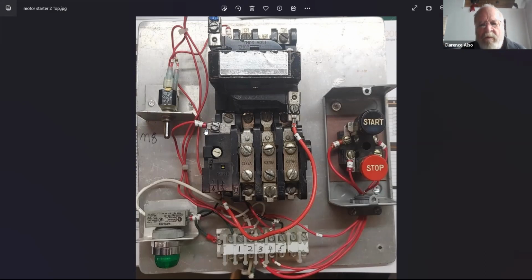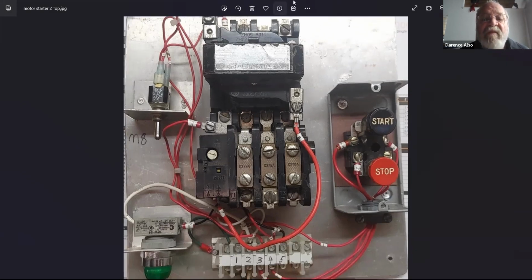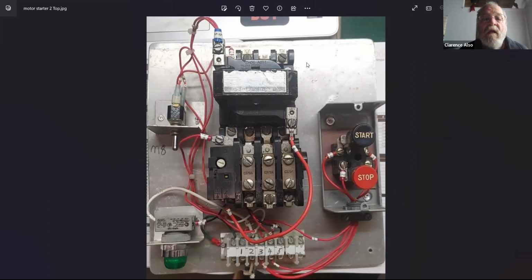On the circuit we're doing, I think we're calling this M9. So anyhow, you had M9 auxiliary contacts, M9 the coil. This is the coil there. You can see a number 6 going to the right side of the coil, and if we went up a bit more, you'd probably see 5 on the other terminal. Remember that terminal number 5 that went to the light and also to the coil? That's the wire right there.